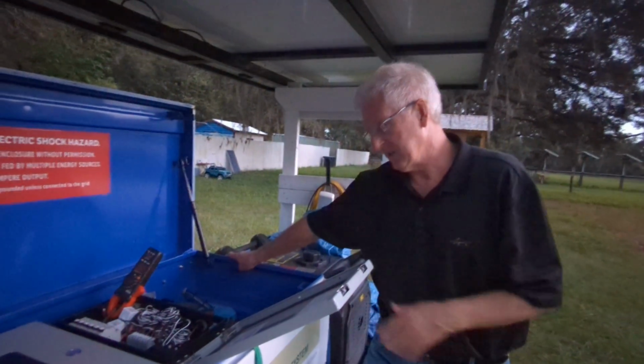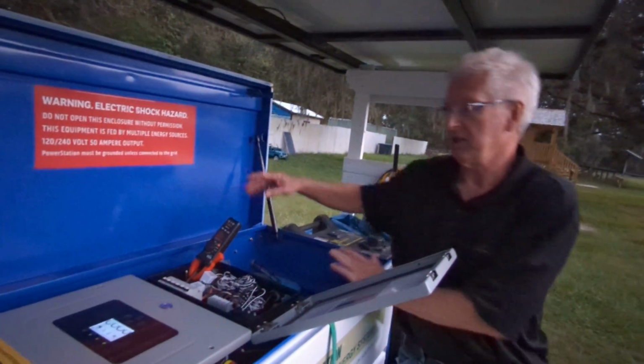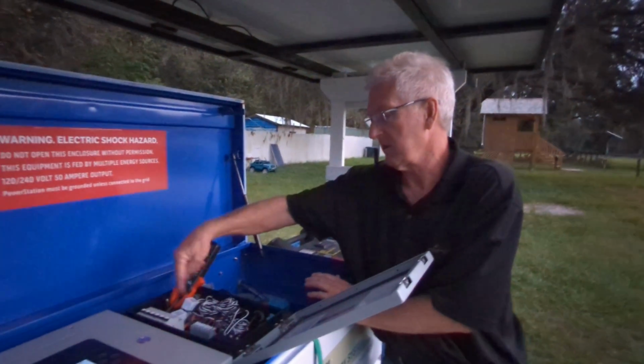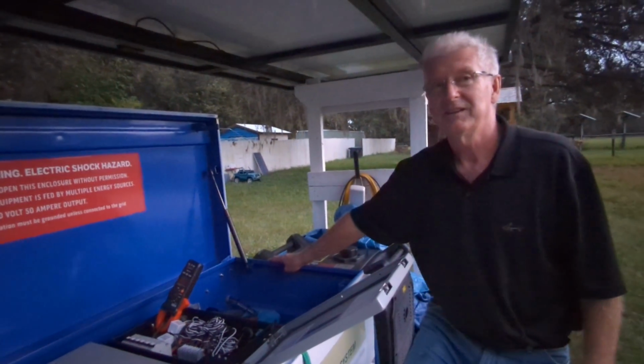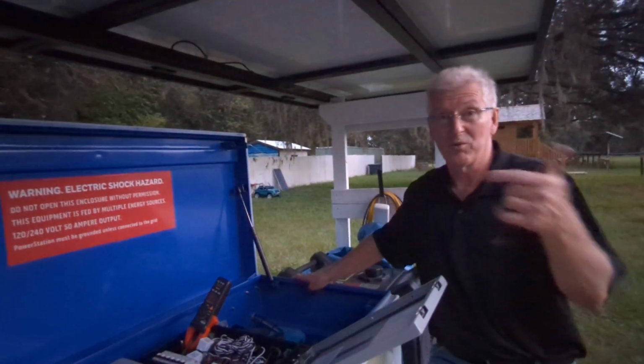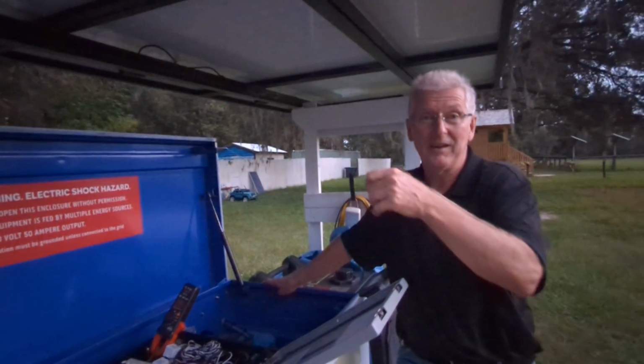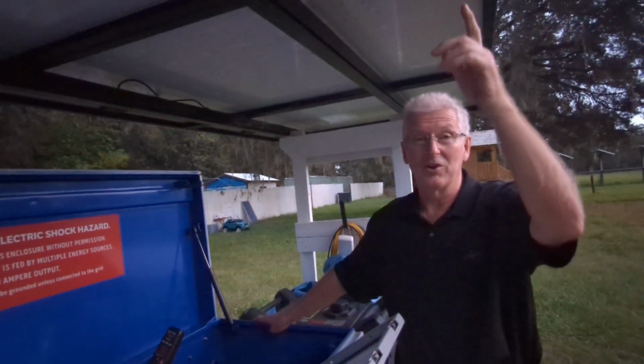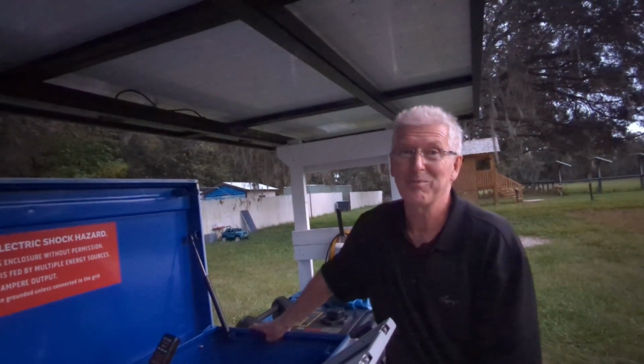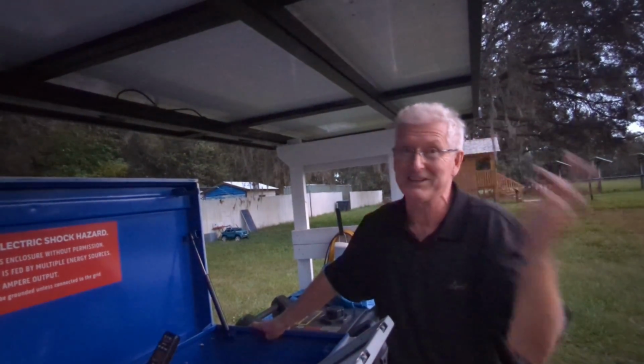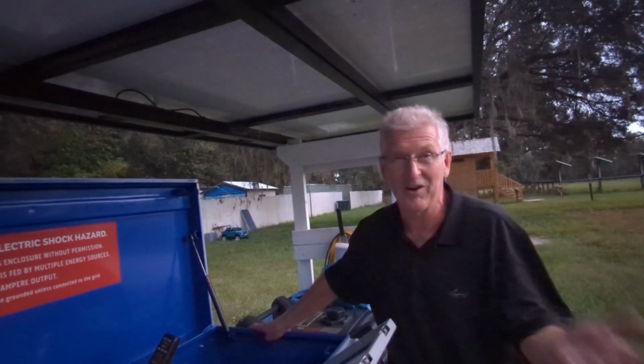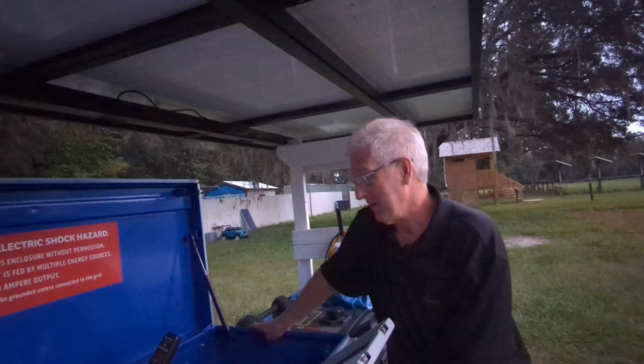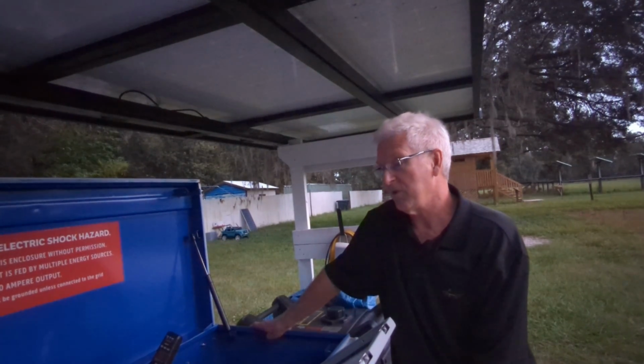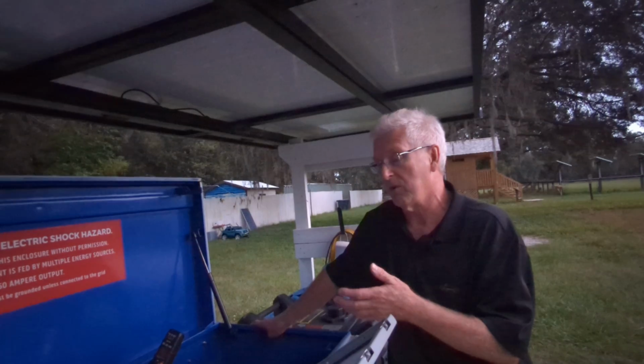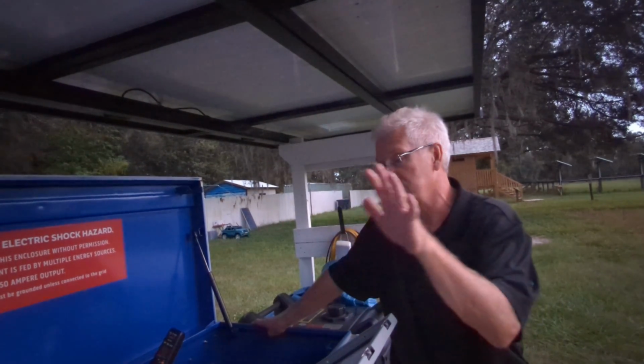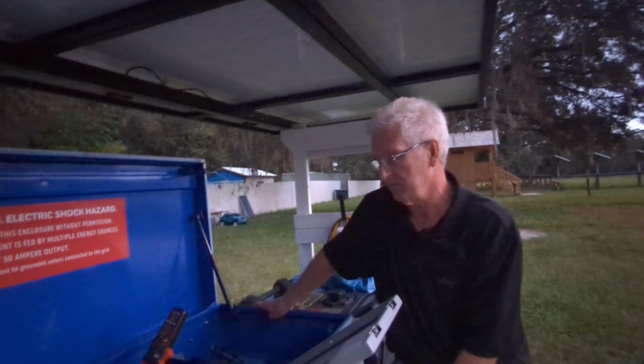What we do have to worry about is there's a maximum pass-through energy on the AC bus. That's all these breakers are connected on the AC bus of 12 kilowatts. So the combination of generator or grid and battery through the inverter and solar can equal 12 kilowatts. And we were up around 11.4 when we had hot plates on, tea kettles on, lights on, converter on, ACs on, right? Yep. But we know it can do it. So whether or not you're on the generator running or whether you're on the grid running, you can pass through, we know, up to 11.5 kilowatts through the system.